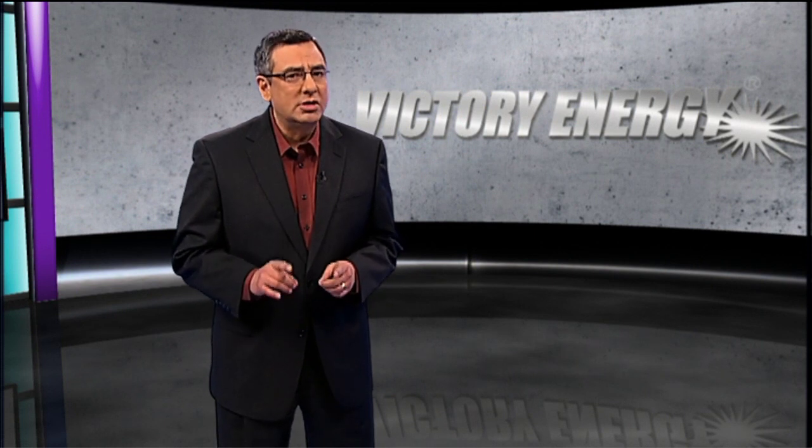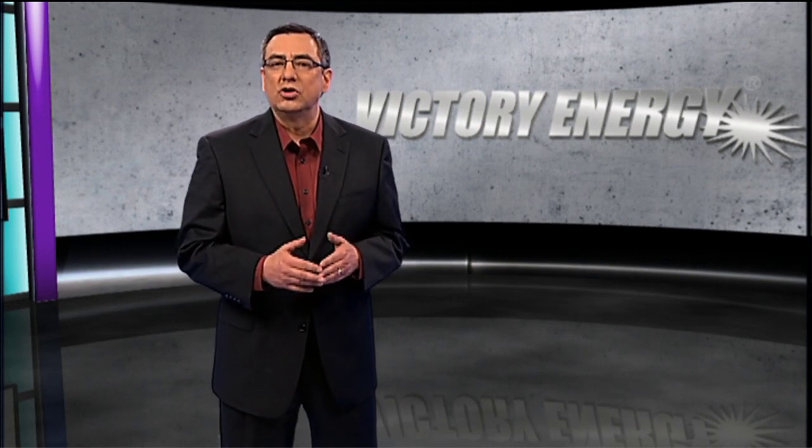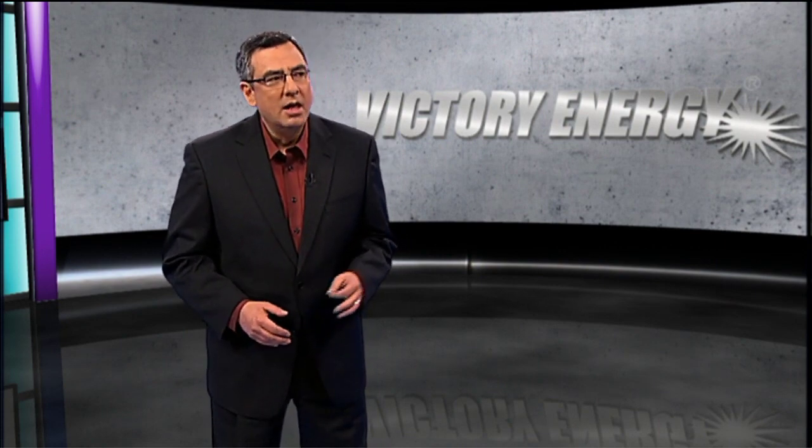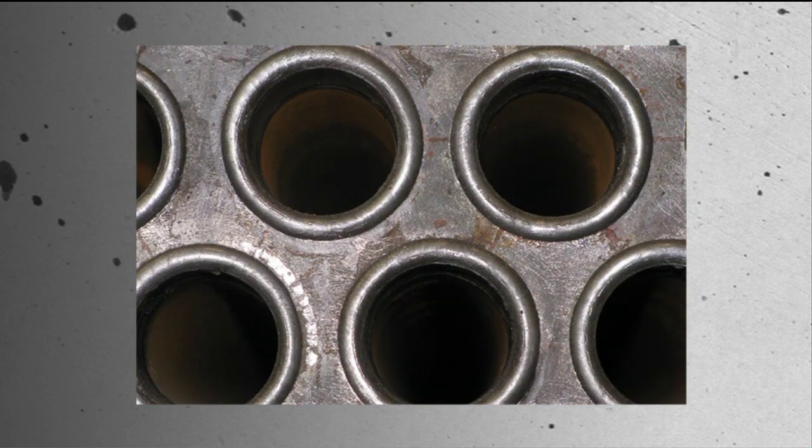But do you know what is different about fire tube boilers engineered in the U.S.? Most fire tube boilers made in the States are designed and built to the strict guidelines of ASME Code Section 4 or Section 1. The metal thickness of these boilers plays a very important role in the design layout for different pressure ratings. All ASME Code Section 1 fire tubes with pressure design ratings of 250, 300, 350, and even 400 PSI will have to meet the thicknesses for maximum safety factors.